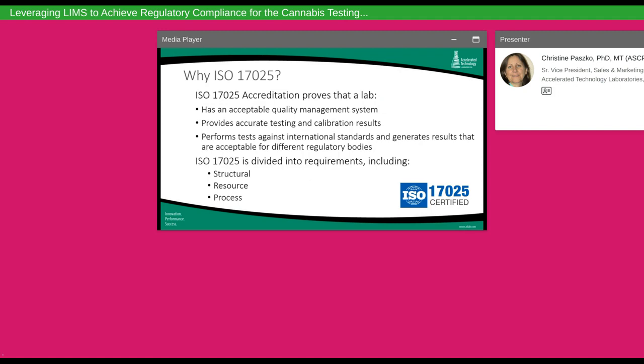Why ISO 17025? It's an International Standards Organization accreditation that proves the laboratory has an acceptable quality management program in place, audited by an independent vendor. It provides accurate testing and calibration results and ensures that laboratory tests are performed against standards generating results acceptable to different regulatory bodies. The ISO 17025 standard is divided into three major requirements: structural, resource, and process.